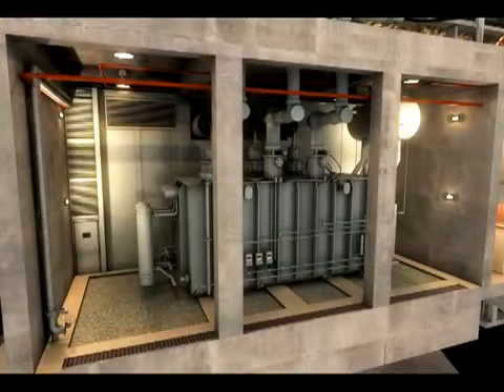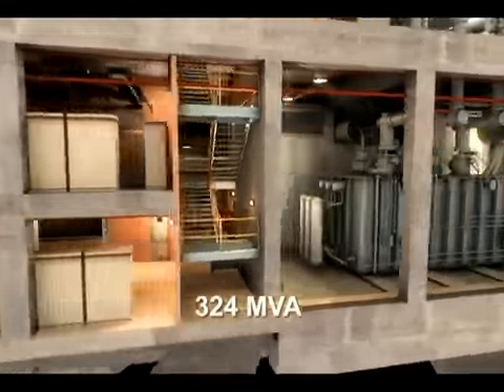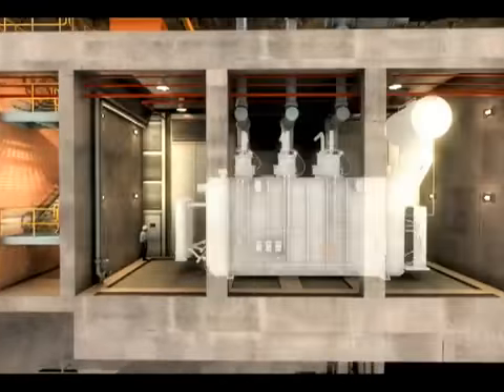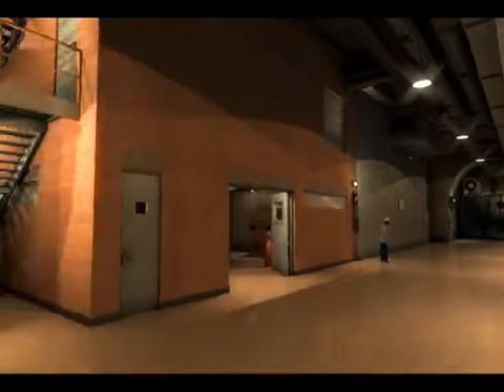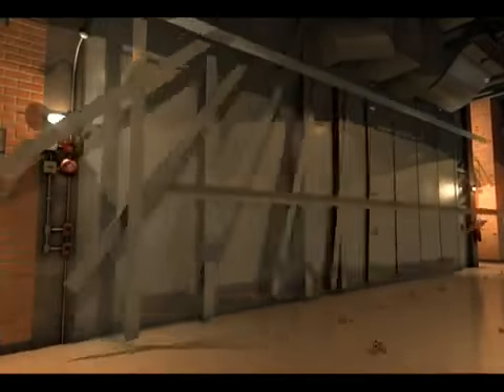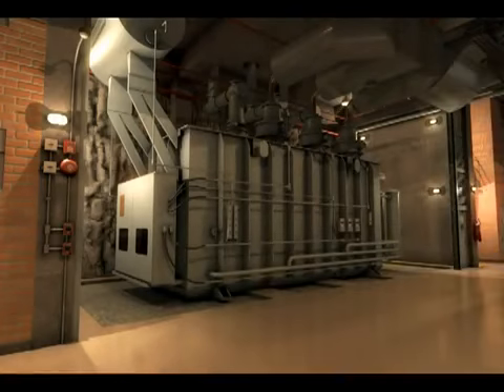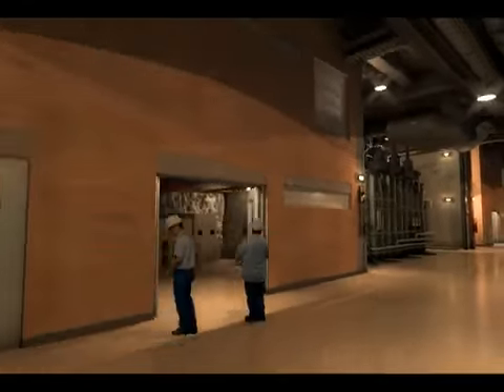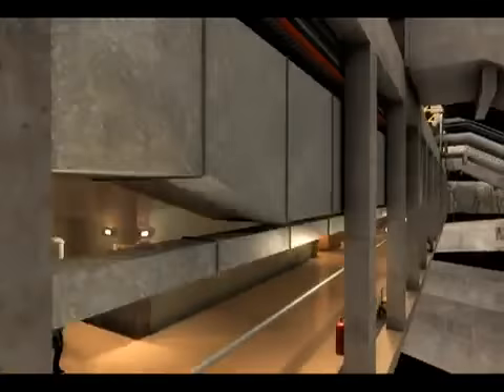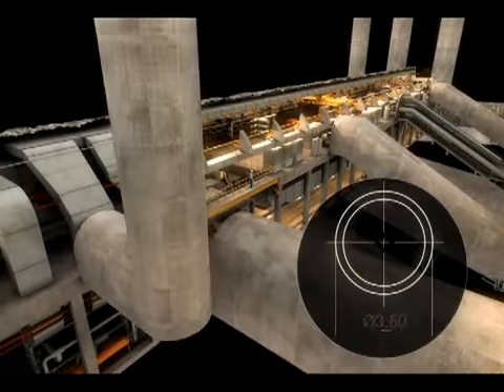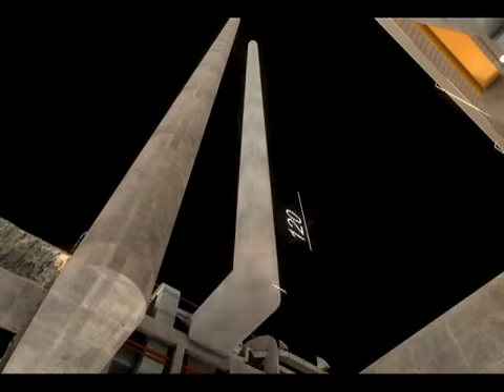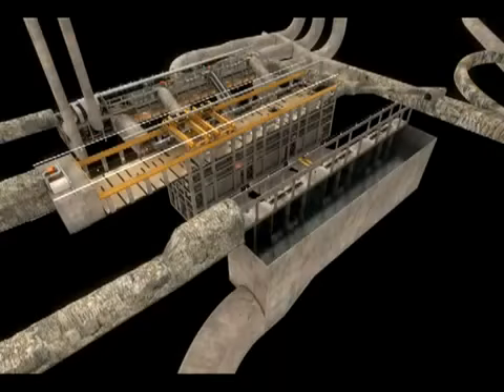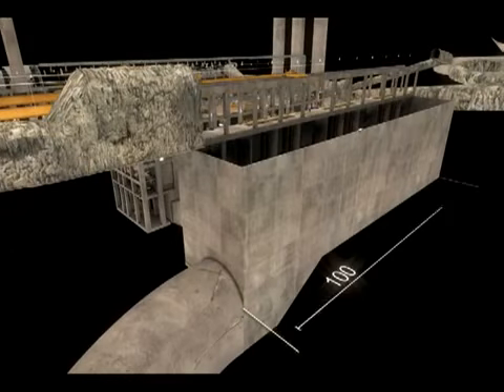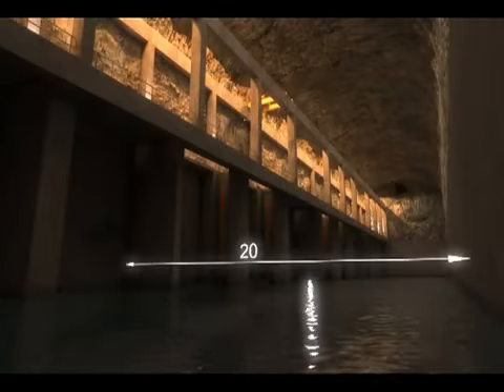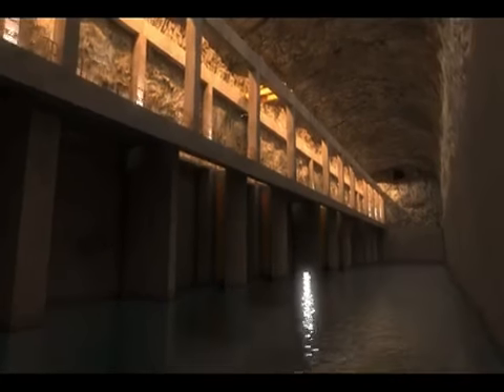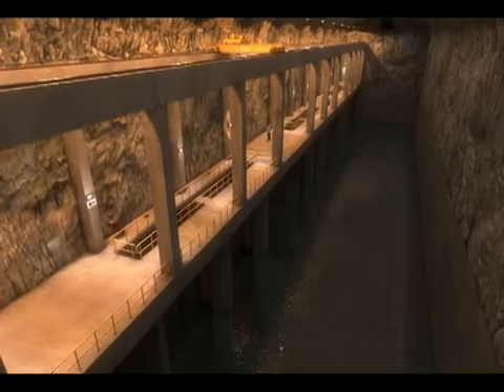The cavern was designed to independently hold the 324 megavolt ampere transformers in order to reduce the risk of damage to generator equipment from potential transformer fires or explosions. This is also the reason why the cavern is equipped with a 3.8 meter diameter gas escape vent that is 120 meters high. The third is the oscillation cavern, which is 100 meters long, 20 meters wide and 43 meters high, and collects water after it has been used in the electrical energy generation process.